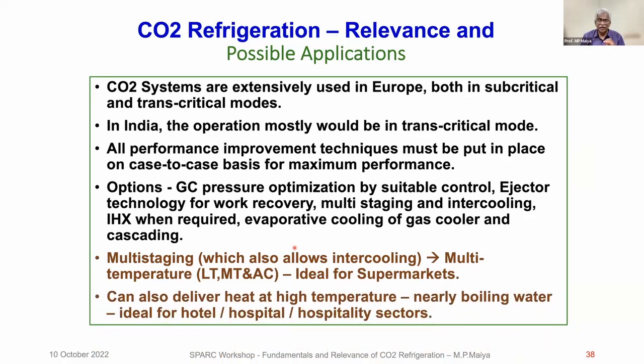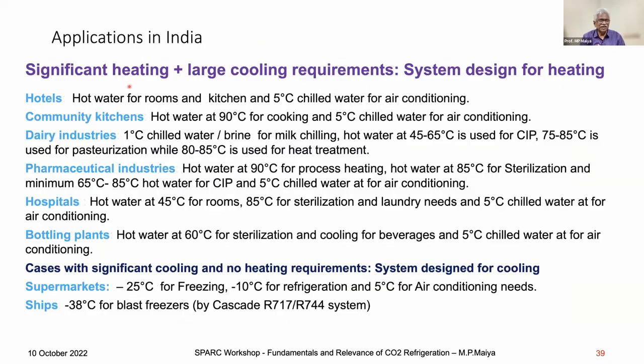Multi-staging we can use. Inherently, it allows intercooling, and once you do multi-staging, many temperatures are possible: low temperature, medium temperature, air conditioning, and also you can heat. So it's ideal for supermarkets, hotels, hospitals, where both cooling and heating are required, or cooling at many temperatures. Low temperature -30, medium temperature -10, AC +5, 10. All temperatures of cooling and heating are required, and you can use it. In India, there are many segments where you can use it, which require both heating and cooling, or multiple temperatures of cooling. All these things can be accommodated by a CO2 system.